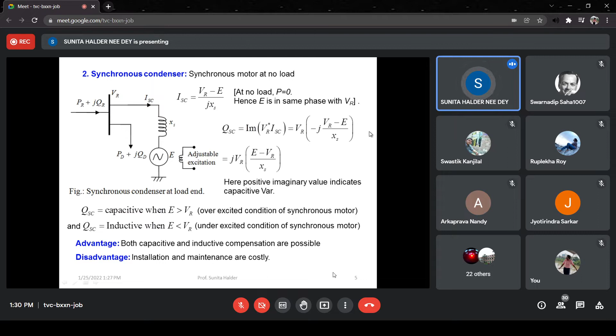Now, what is the advantage? Here, by excitation control only, we can get both inductive and capacitive type of compensation. But the disadvantage is it is costly. Installation is tedious. At the same time, it requires regular maintenance because it has rotating parts, so bearings, all these things are there. So lubrication and all other maintenance will be required more for the synchronous condenser. Otherwise, it is a very good compensator because we can get a wide range of compensation from inductance to capacitance very easily.